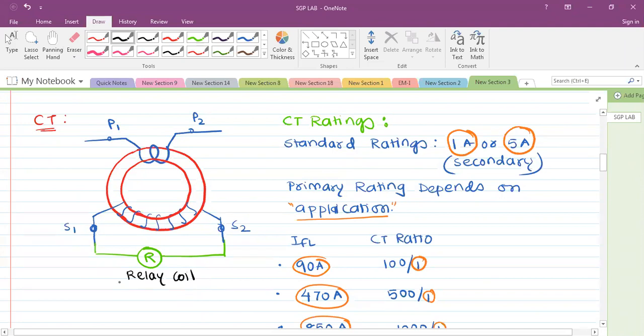So what is the advantage? Suppose as we have this 1 ampere CT secondary rating, the relay coil can also be designed with either 1 ampere or 5 ampere capacity. So that will standardize the relay design.